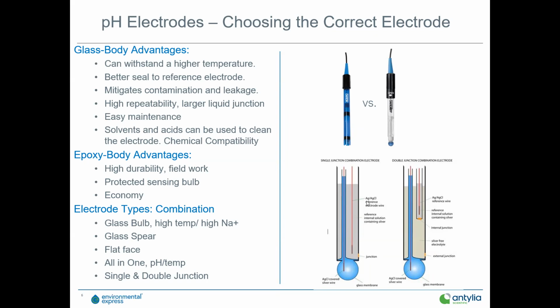The big difference here is a single junction. This is pictured kind of the lower center of this slide. As you can see, the glass bulb is what's doing the measurement. The liquid junction is where the electrolyte actually comes out into contact with your sample, as well as that glass bulb. When poisoning ions are introduced to pH electrodes, that's how they attack the electrode. They will actually migrate across the junction and attack this little silver chloride reference tip. That is kind of the main stability point of this single junction electrode. And when the liquid junction either dries out because it's not stored in a soaker bottle or it's not properly hydrated, that's one of the key issues you'll see.